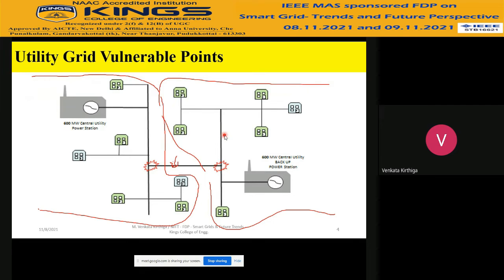Because normally if you look at the load curve, we don't have all the connected load coming into picture at all times - that is the information shared by the load curve, when which load requires energy. So suppose if something happens by accident or unexpectedly all the connected loads come into picture, or they are just switched on for some reason by mistake, and if it goes to some 800 megawatts or so, then definitely this line cannot withstand its capacity. So such rare occurrences can happen, which will always force this line to be opened. That is why these 2 points are considered as vulnerable points.